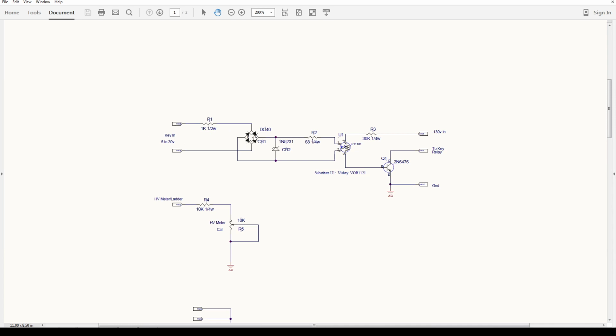Then it comes into the bridge here. This Zener diode clamps any voltage beyond what's allowed across the LED inside the solid-state relay, which is a high-voltage solid-state relay rated around 300 volts on its relay side.